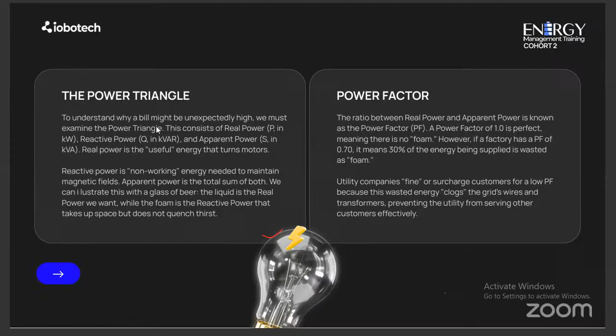So if we use the meter that is giving us 0.7 or 0.75, and then we use your neighbor's meter that is showing a power factor of 0.9, who is at the losing end? You realize that we are cheating your neighbor whose meter is displaying correctly, who is not using an inductive load. So that is why power factor is very, very important when billing is happening. Whenever a meter is showing a power factor below that threshold, we no longer bill you with your energy meter. I hope that what I've said answers your question already.